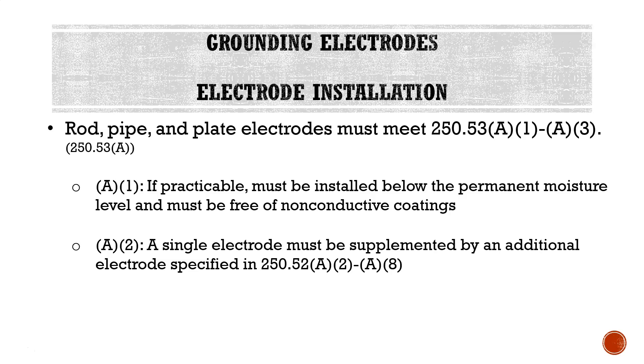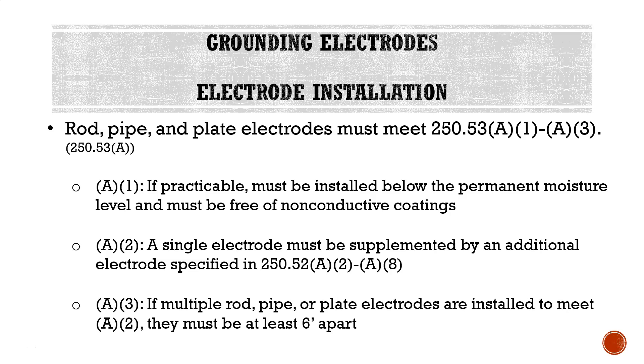A2: a single electrode must be supplemented by an additional electrode specified in 250.52 A2 through A8. In other words, if we're using a rod, pipe, or plate electrode, we have to use some other type of electrode with it as well. A3: if multiple rod, pipe, or plate electrodes are installed to meet A2, they must be spaced at least six feet apart. A typical installation in a residential application is to install a ground rod, then per A2, since you used a single rod electrode, you install an additional electrode — commonly a second rod. Per A3, they must be spaced at least six feet apart.